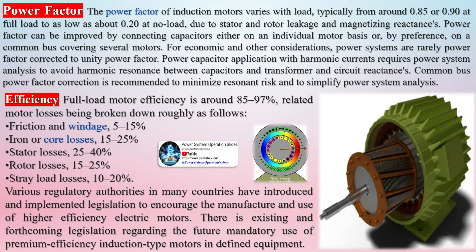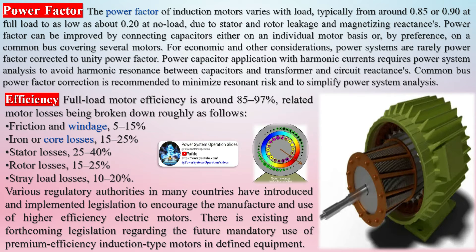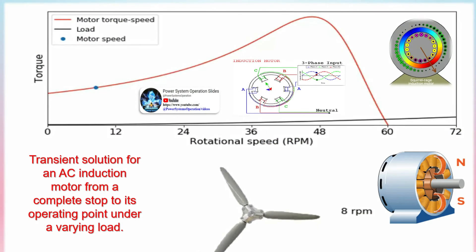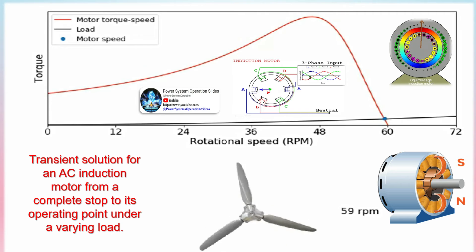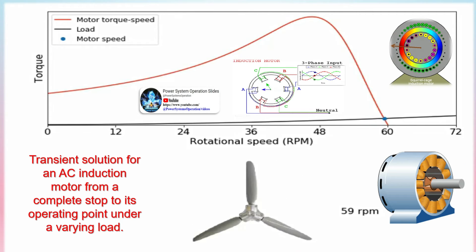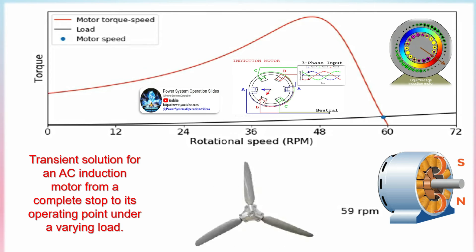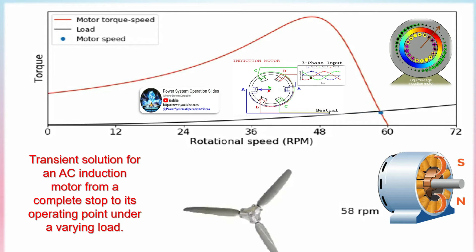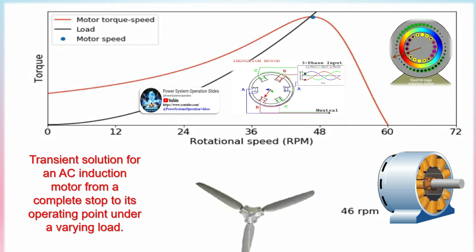The power factor of induction motors varies with load, typically from around 0.85 to 0.90 at full load to as low as about 0.20 at no load, due to stator and rotor leakage and magnetizing reactances. Power factor can be improved by connecting capacitors either on an individual motor basis or, by preference, on a common bus covering several motors. Power systems are rarely power factor corrected to unity. Power capacitor application with harmonic currents requires power system analysis to avoid harmonic resonance between capacitors and transformer and circuit reactances. Common bus power factor correction is recommended to minimize resonant risk.